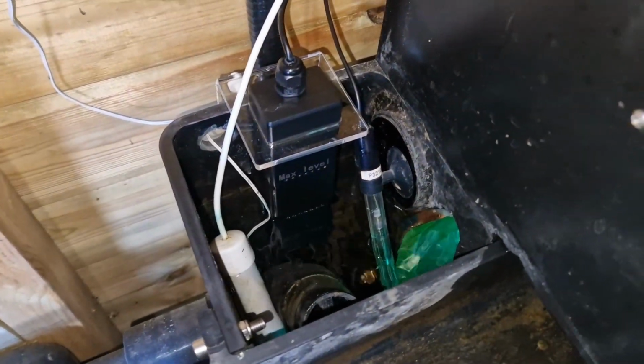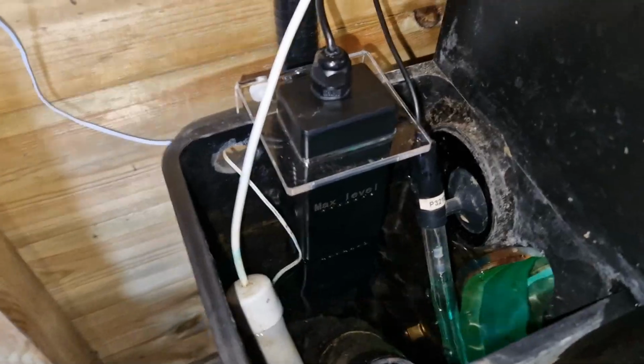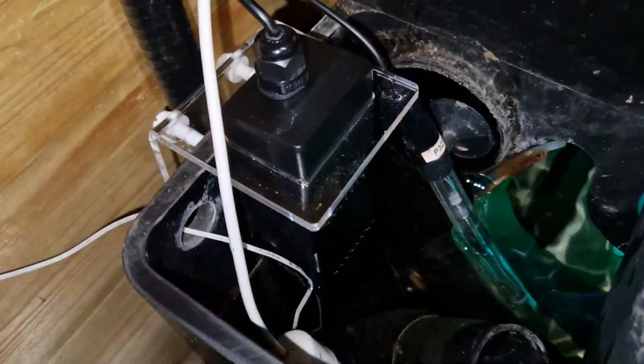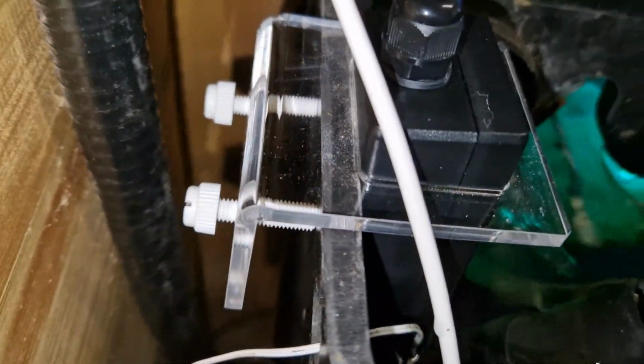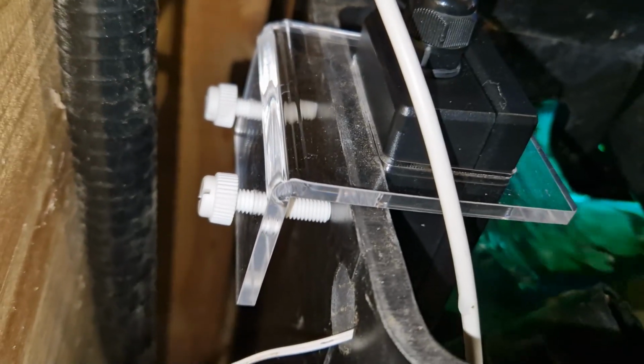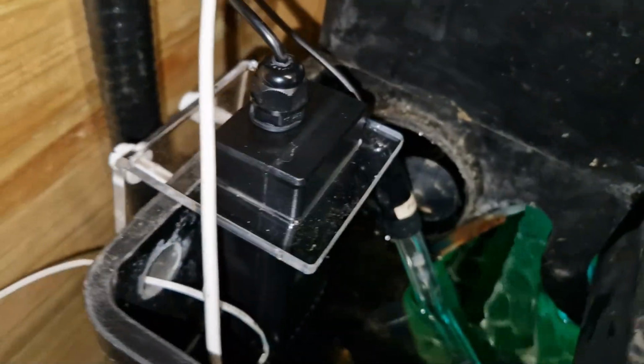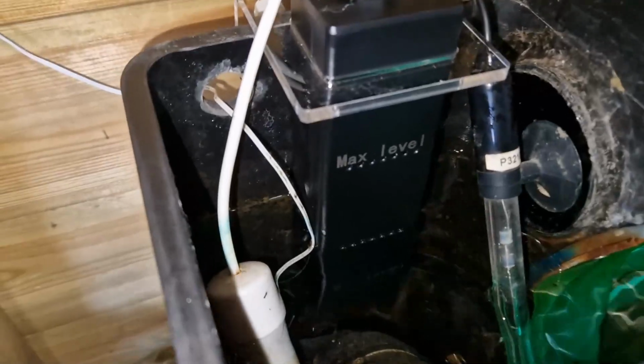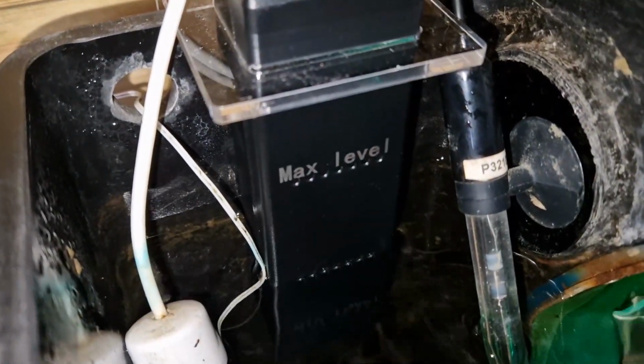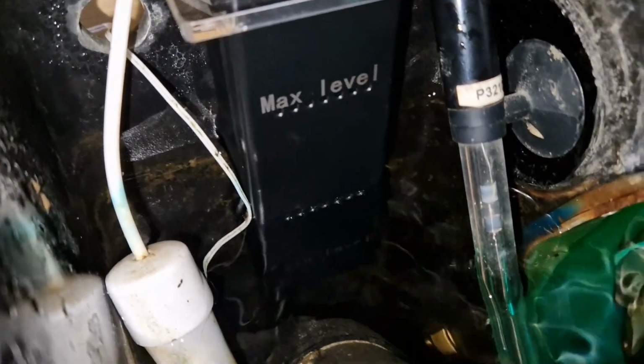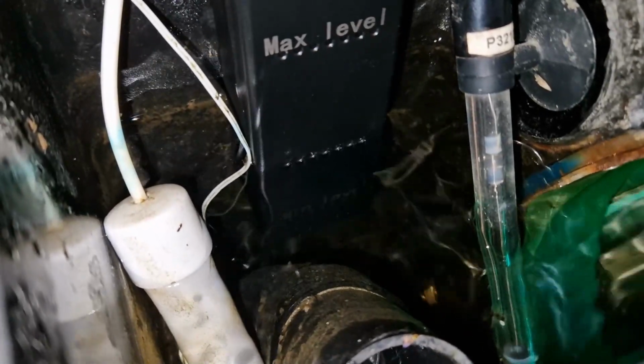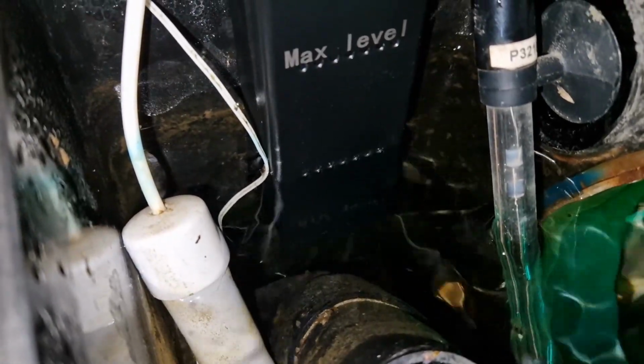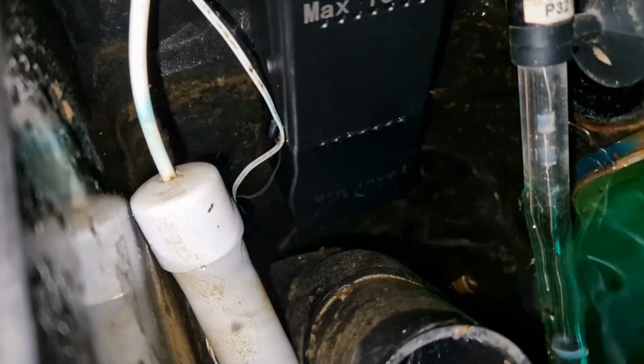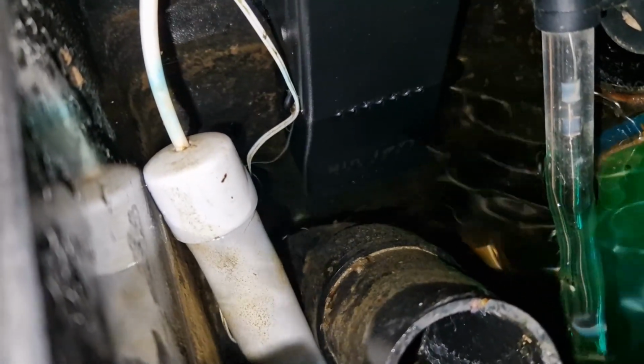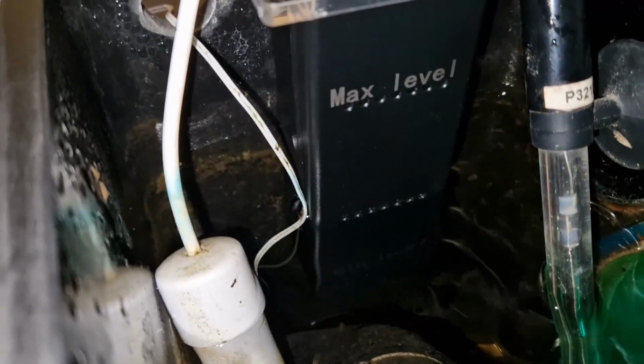Right, so that's the probe in the filter, guys. Like I say, it just secures on with this bracket. You've got a couple of screws that you tighten up that secures it onto the back of the filter like that. And then on the probe itself, it's got a max level, and I don't know if you'll see it, but at the bottom down there it's got a minimum level. So you've got to make sure it's submerged in the water between those two levels. So that's where I've got mine set.